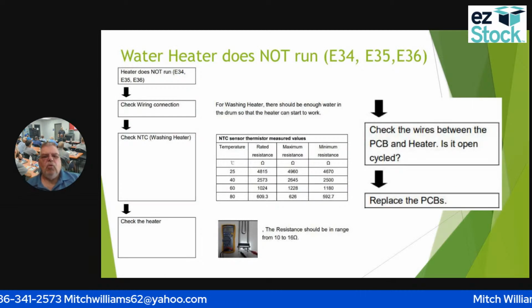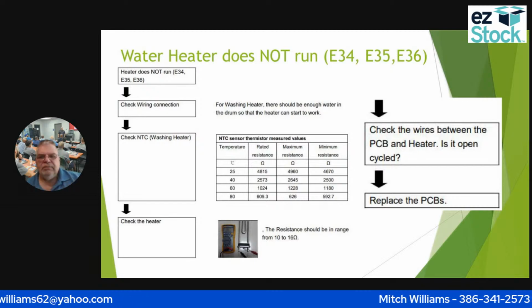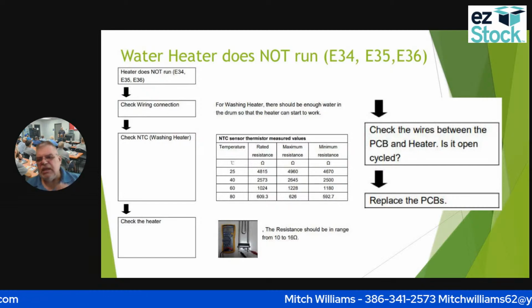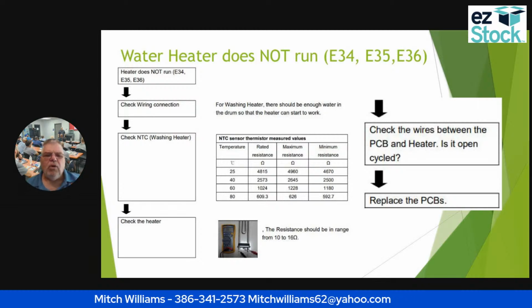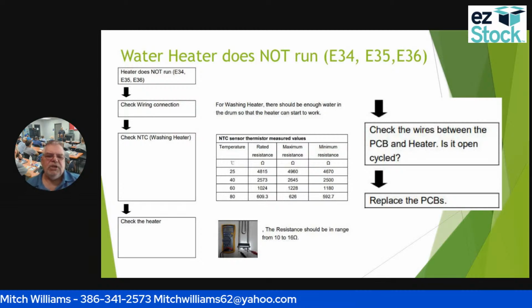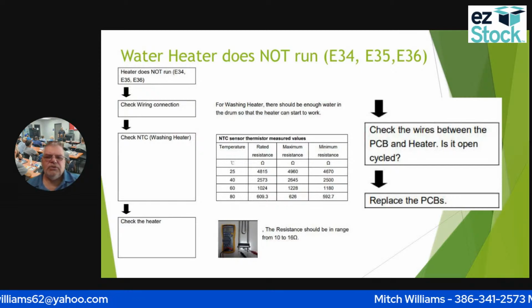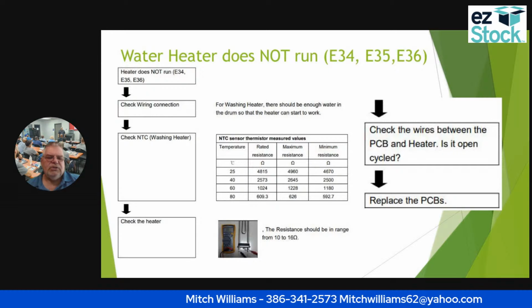Okay. The water heater does not run. Okay. If that's an E34, an E35, or an E36. So if the water heater doesn't work, I'm going to check the wiring to the connection. Okay. So there should be enough water in the drum so the heater can start to work. I'm going to check the NTC.